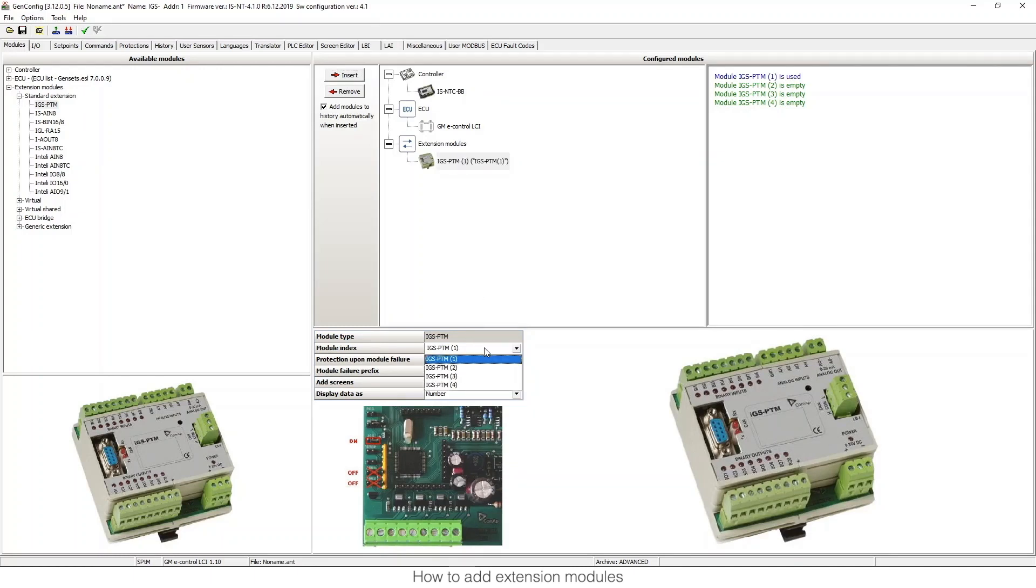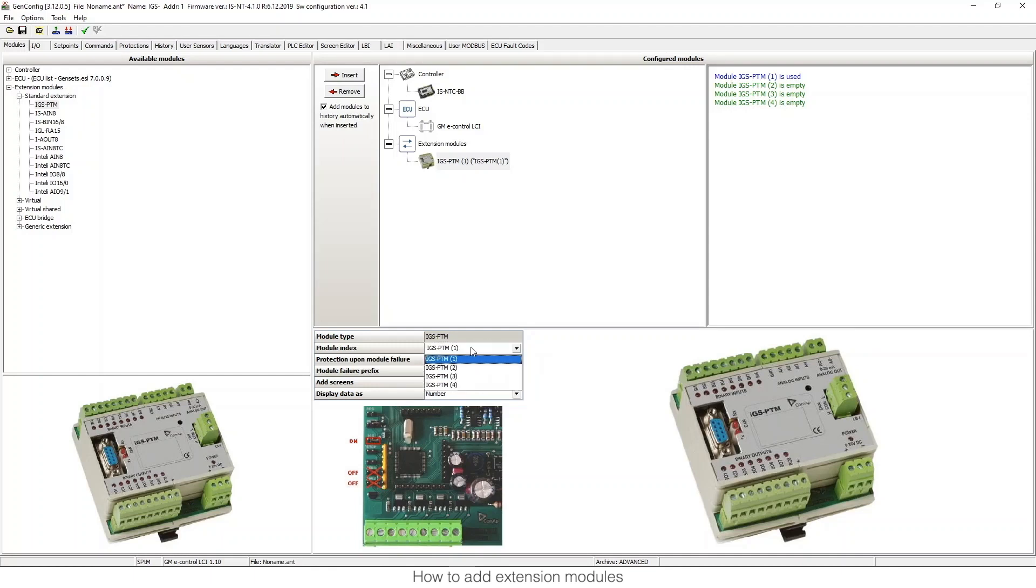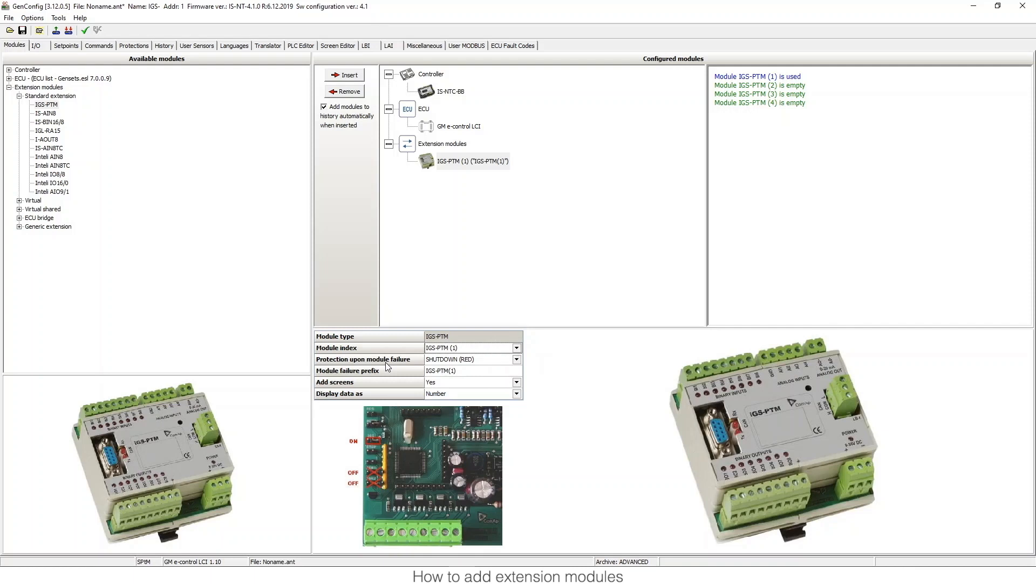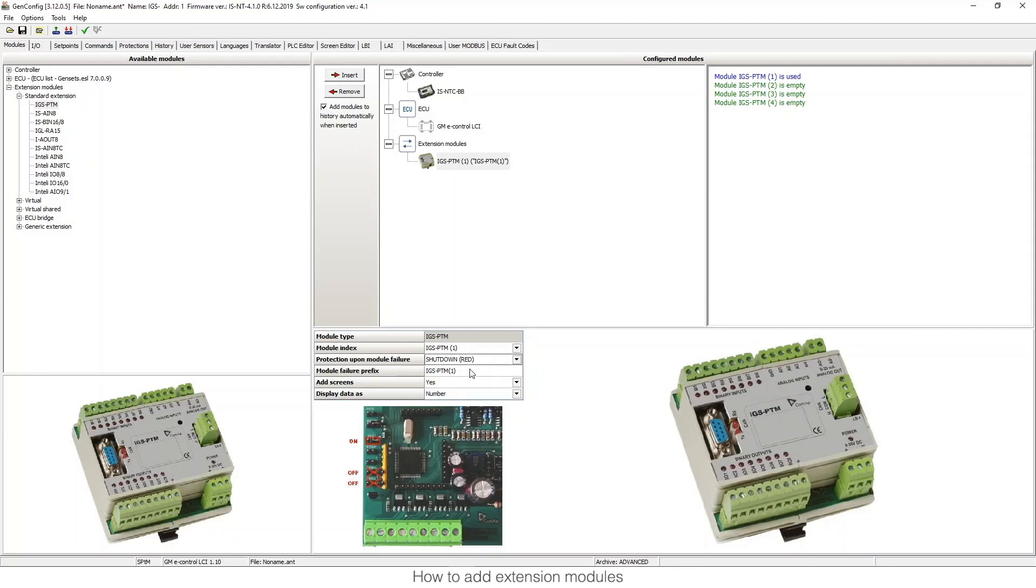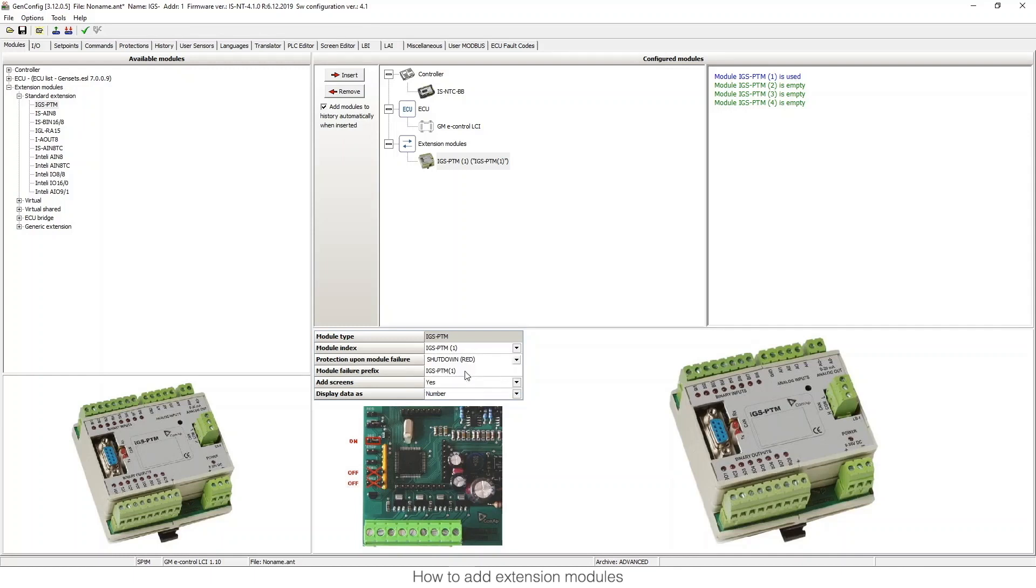Now we have some configuration options we can do. Here for example we can choose the CAN address. The CAN module is using CAN1 for these modules. You can also choose the protection level in case there are failures in the communication. You can use no protection at all, just a warning, or a shutdown. When there is a mistake in the communication, there's a shutdown of the controller.